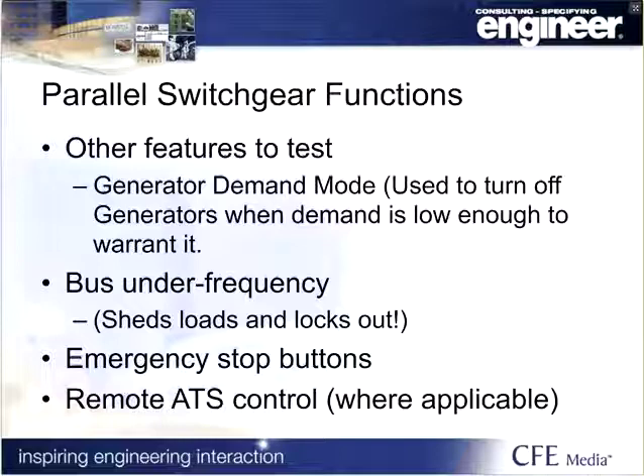You also want to look at your e-stops. Typically, most AHJs and the code require e-stops outside of the building, or outside of the generator room I should say, and they're meant to turn off the engines. For some building types you require remote ATS controls, such as a high-rise. So you will have to also check that as well.